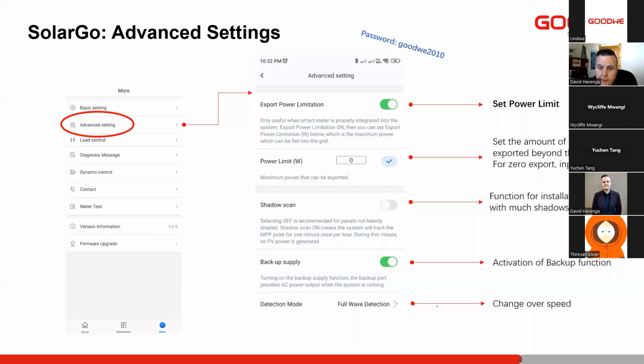Next, we have the grid changeover speed or detection. It's always recommended, for full detection of equipment down the line as well as seamless changeover, to have full wave detection. With full wave detection, you'll have your 10 milliseconds changeover. You can select half wave or wave right through. That will delay the changeover on the backup. That's used for areas where we might have momentary voltage spikes slightly above or slightly below the grid recommended voltage, to give the inverter a bit more time before it disconnects from the grid. Only if we have very volatile grids that jump up and down, we can adjust that. But if we want the inverter to disconnect to protect equipment, we can leave it on full wave detection.